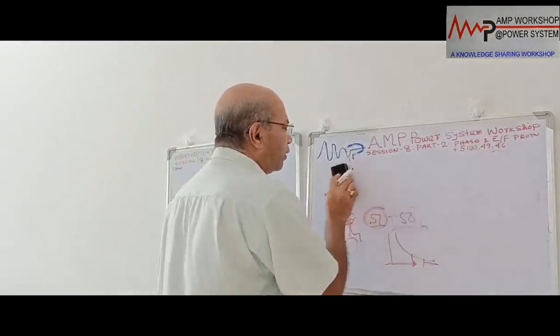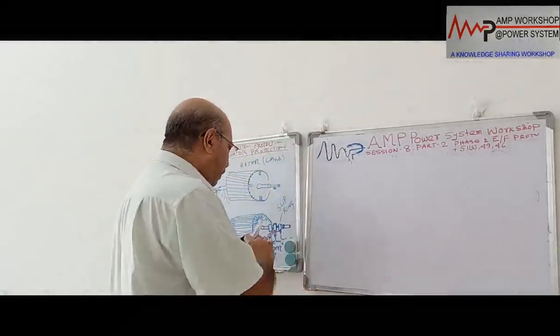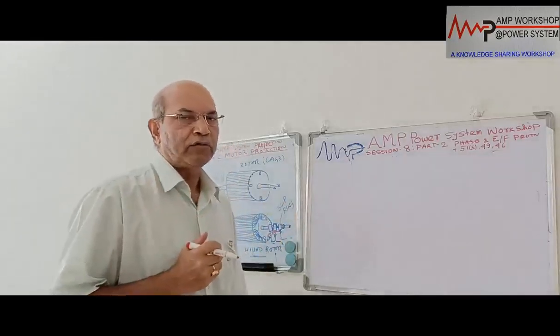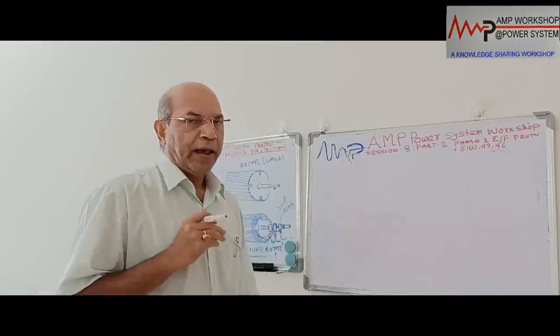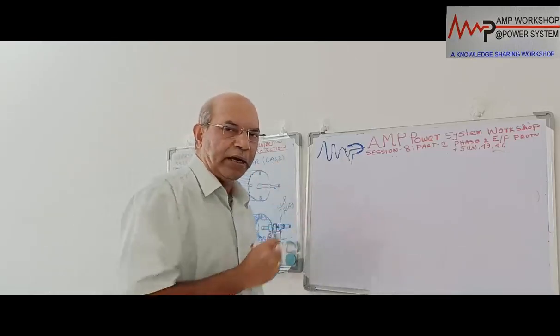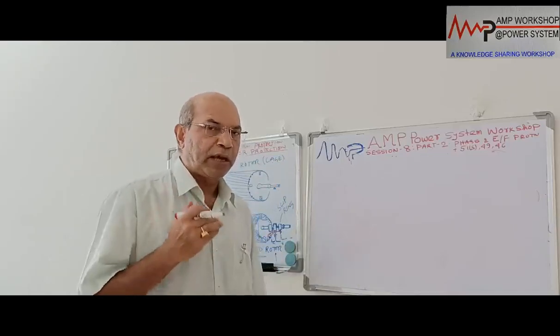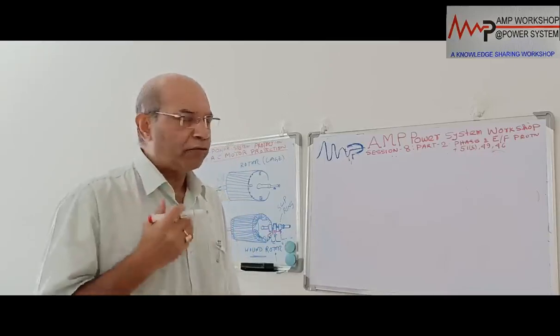And now we come to the situation of the differential protection. Now it may happen that the system has no adequate capacity to feed for this instantaneous overcurrent relay. In that case, the instantaneous overcurrent relay will not operate, and only the IDMT overcurrent relay with a time delay is provided. Maybe in the system the motor is so important that we cannot wait for that time. The motor may fail in that case. That is one of the occasions.